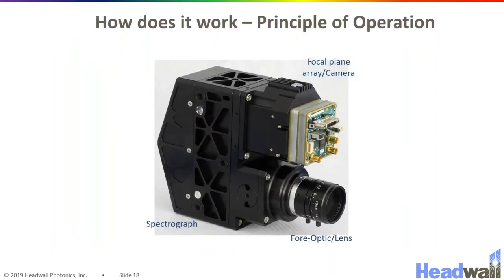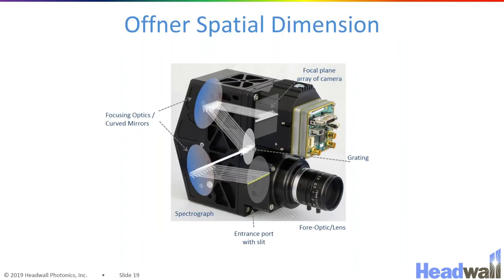So how do the optics of the system work to achieve this? If we cut away and see how the optics look on the inside, this fore-optic lens is projecting the image of your scene onto a slit right here. And that slit is then put into a set of two concave mirrors and one convex mirror, and that set of optics will re-image this slit onto the focal plane.